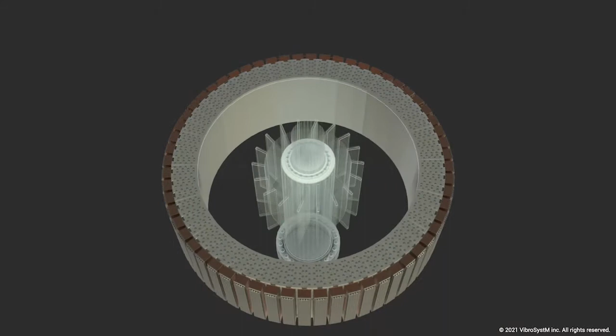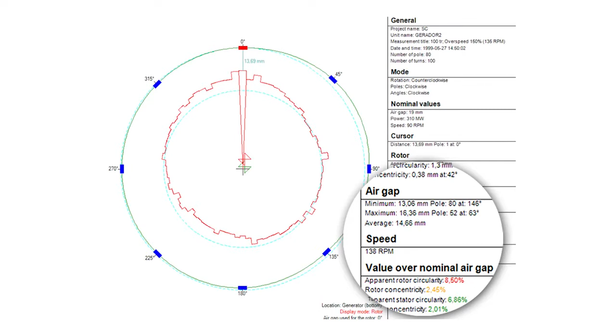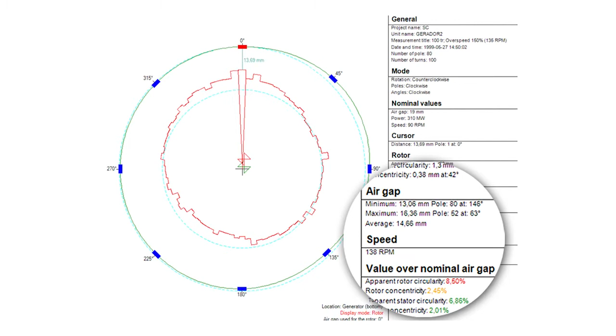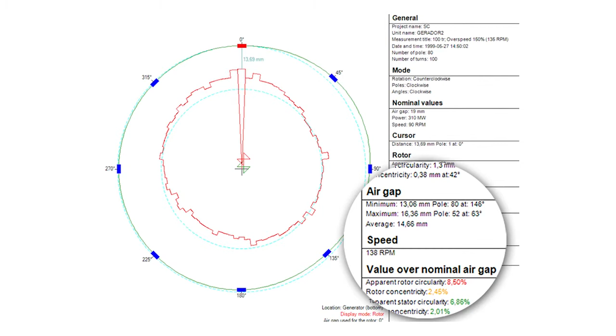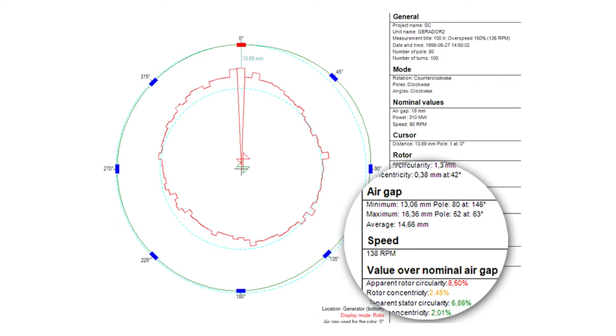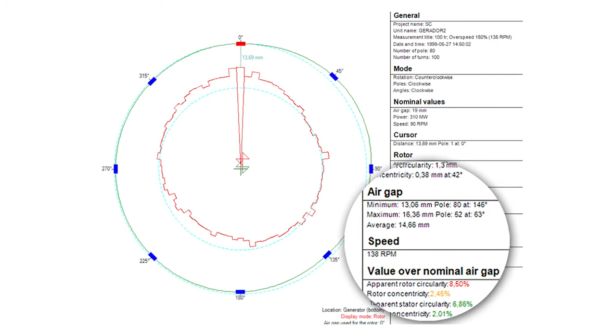It was quite fast. I think they went up to 154% speed, which is very fast for large units like this. And we took the readings during that test and we started to analyze the results. If you looked at the graph, you could see that the air gap during the overspeed was much smaller than the design. The design was 19 millimeters and the results were around 14 millimeters. So the air gap during this test was much smaller, but that's to be expected. Again, the excessive centrifugal forces caused the rotor to increase in size, so therefore the air gap is smaller.